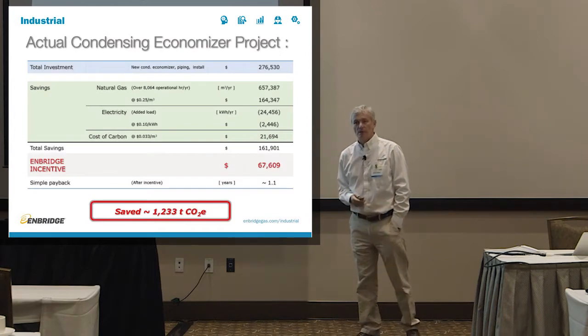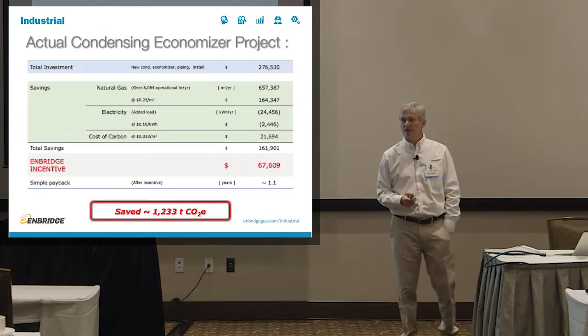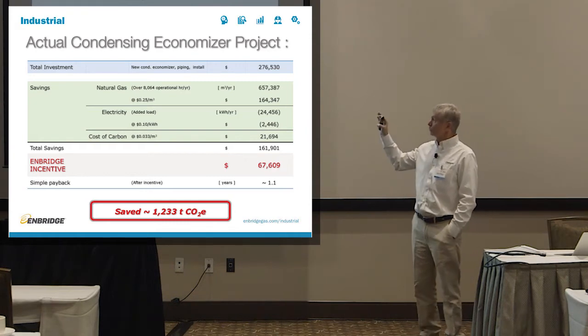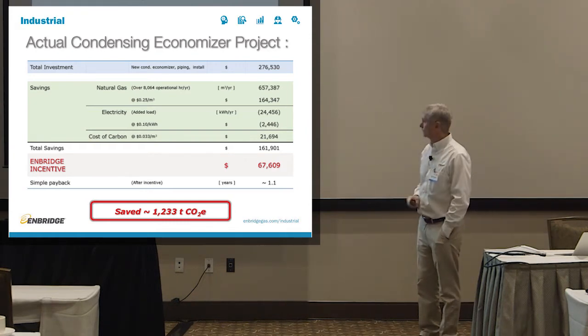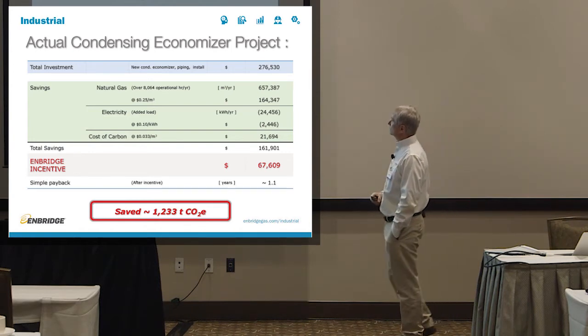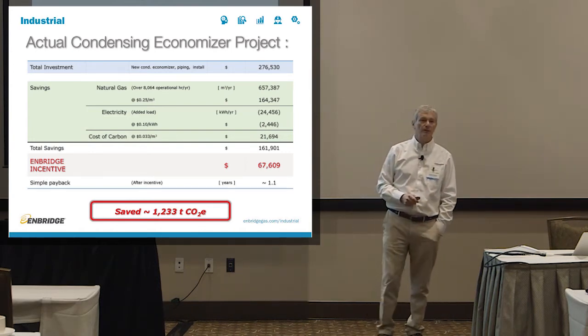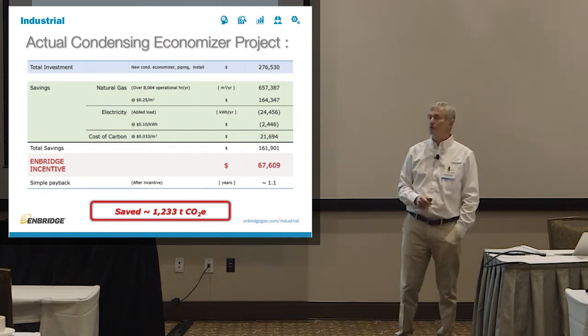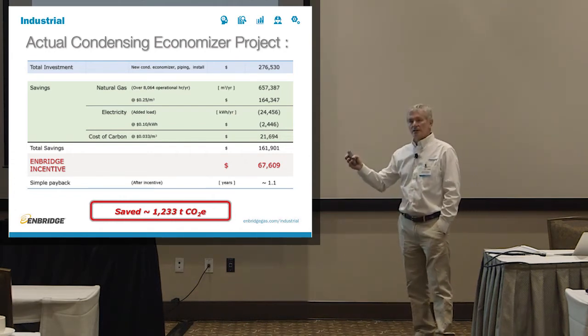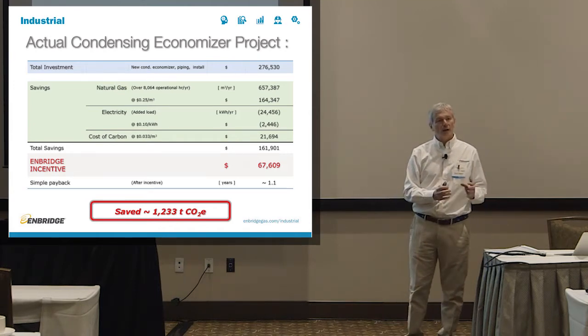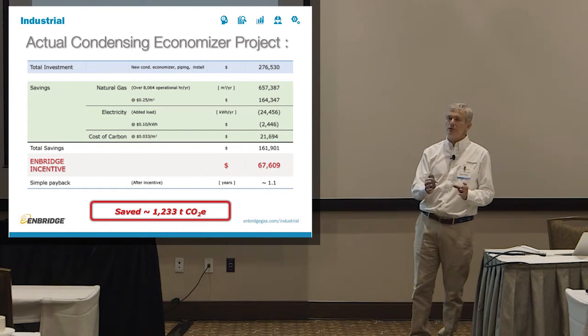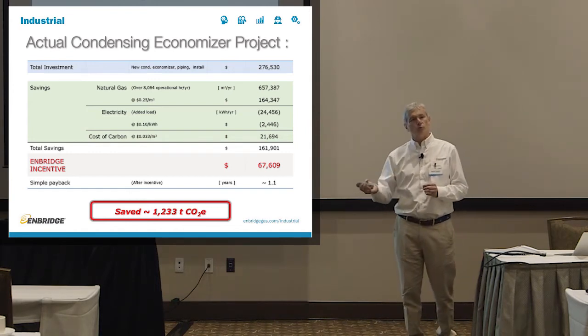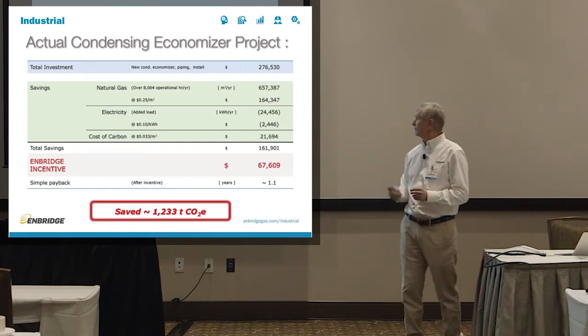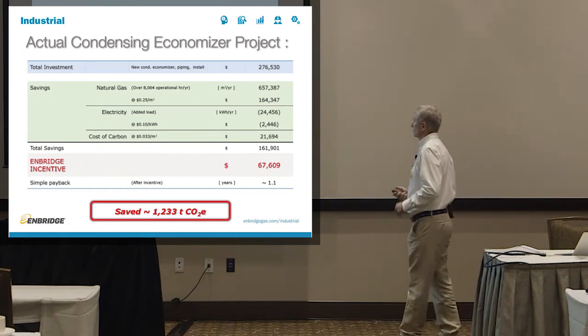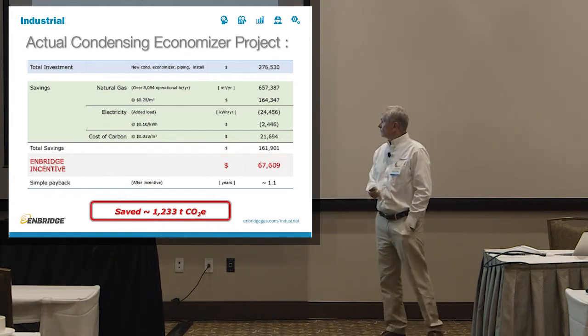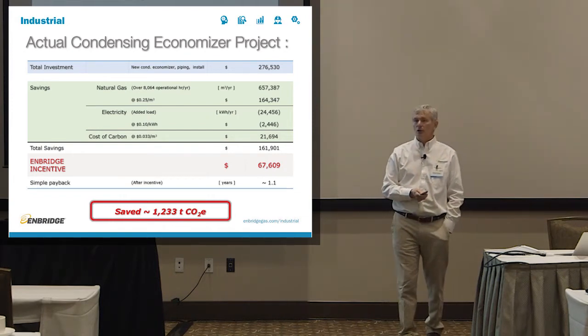And this is the project I'm talking about. $276,000 investment. It's a relatively large condensing economizer. Installed, the whole cost, there is nothing else there. But it saved them, look at the savings, 660,000 cubic meters of natural gas every year. They added a little bit of electricity because when you're installing a condensing economizer offline, which means that two boilers can use the same condensing economizer, you have to use a fan to pull the flue gas out of each stack. It's not a big cost. For the savings of $162,000 every year.